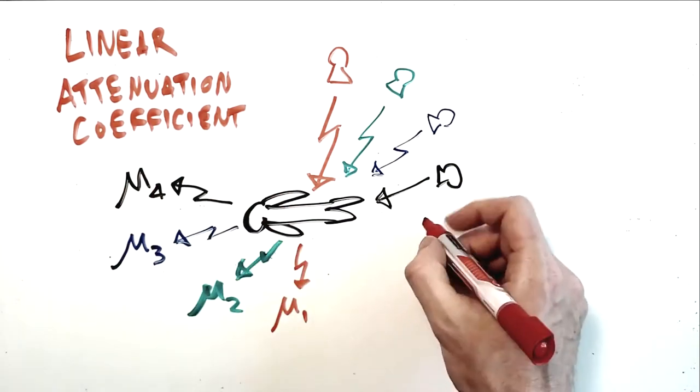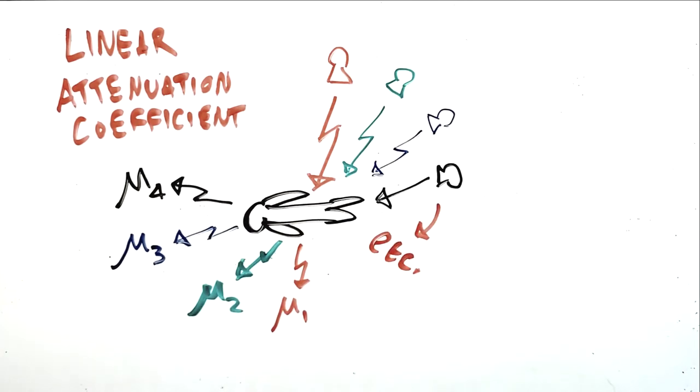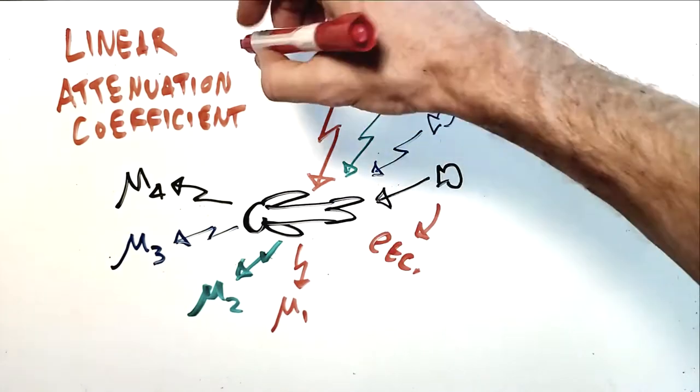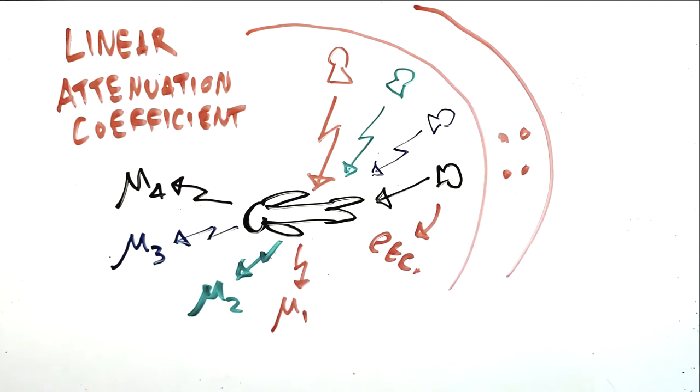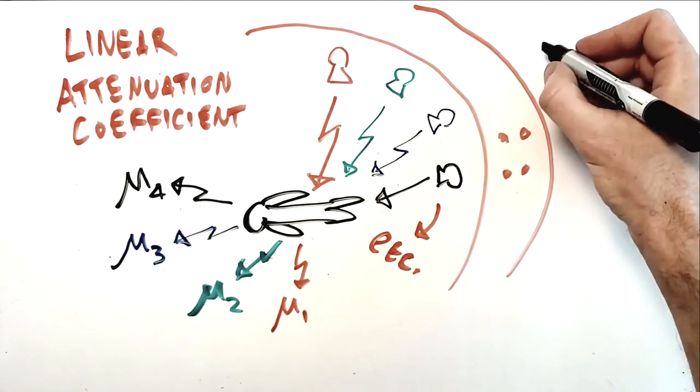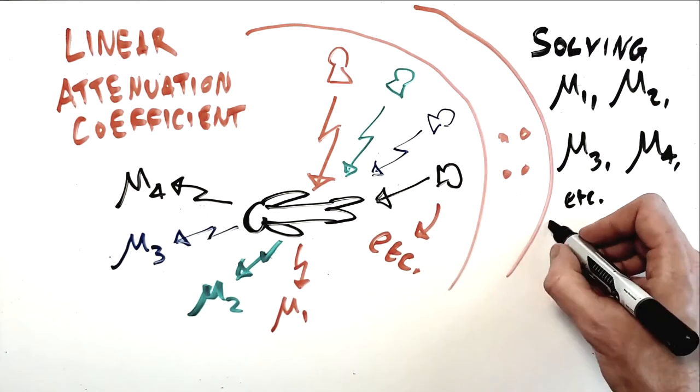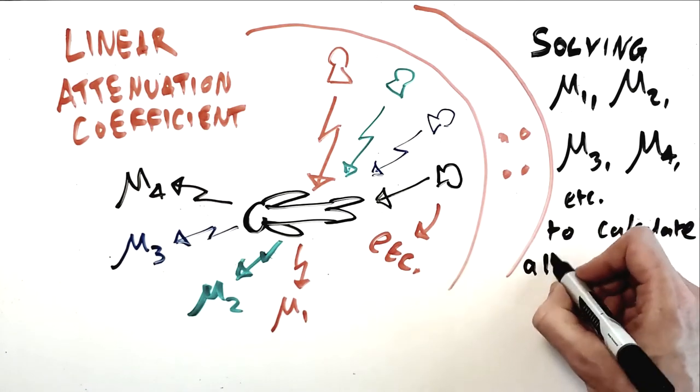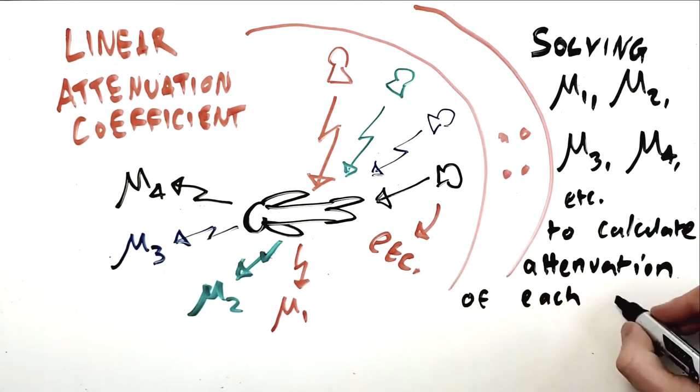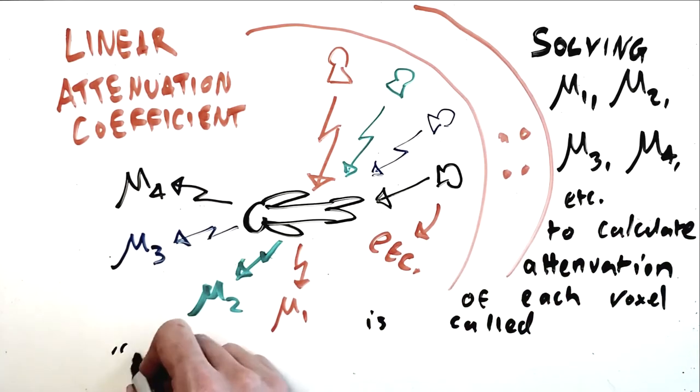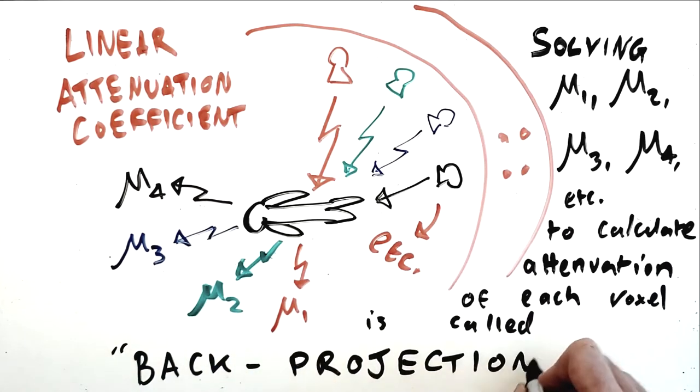This makes for a complex mathematical situation in which the attenuation pathways from all angles need to be unwoven in order to map out where in 3D space x-ray attenuation has occurred. This process of tracing attenuation back to the voxel in which it happened by calculating the linear attenuation coefficient through each voxel from various angles is known as back projection, and that process is the basic building block of reconstructing a CT image.